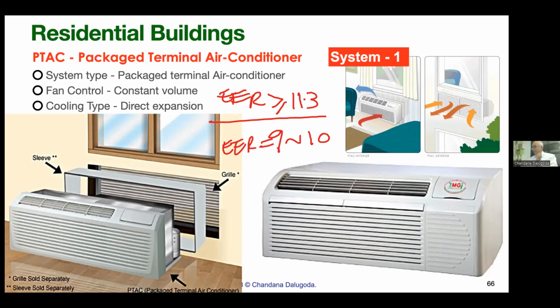What is EER? Energy efficiency ratio. Simply, EER equals cooling capacity in BTU per hour divided by power input in watts. The higher the EER, the higher the efficiency. So when you select an air conditioner for your green building or a net zero building, you like to find 11.3 EER unit or higher unit for residences.